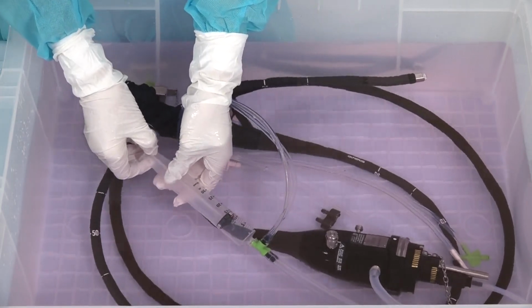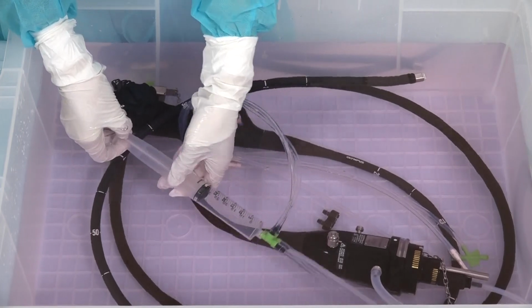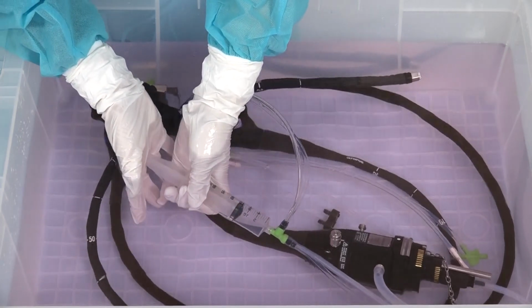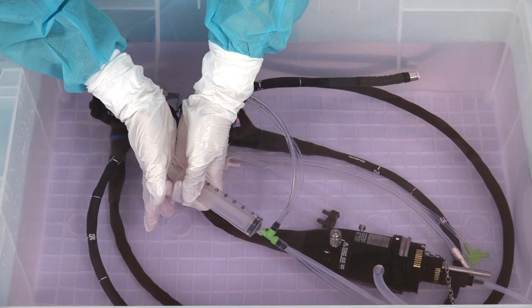Confirm that no air bubbles exit from the distal end during the last flush. If air bubbles still exit during the 6th flush, flush the channel with the disinfectant solution until no air bubbles exit.